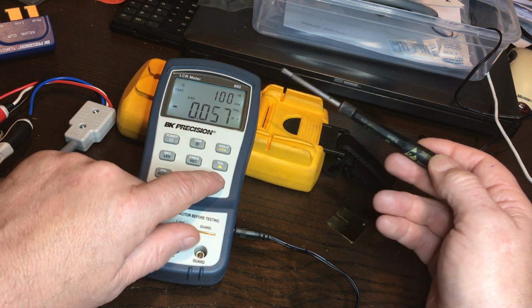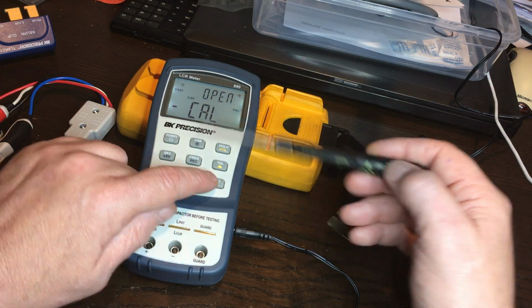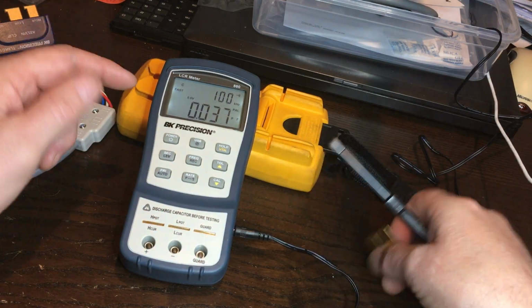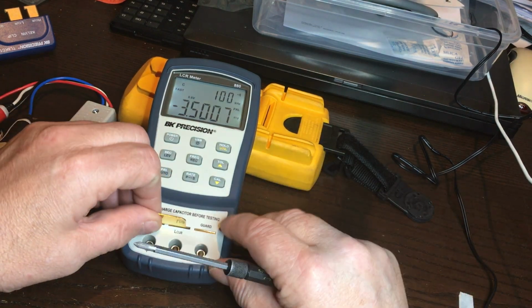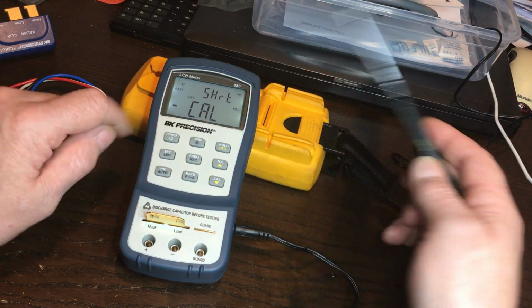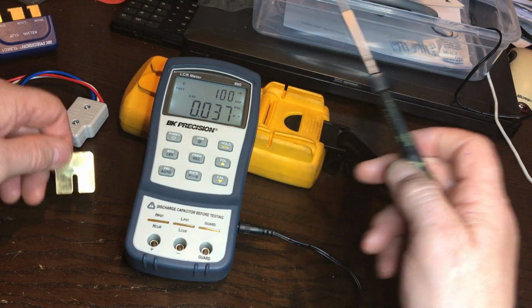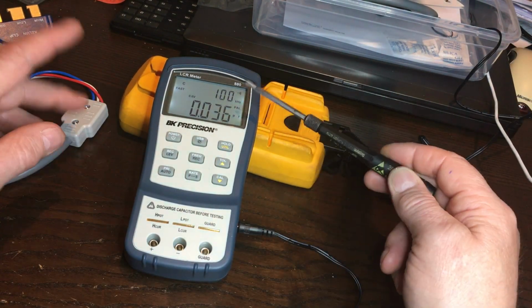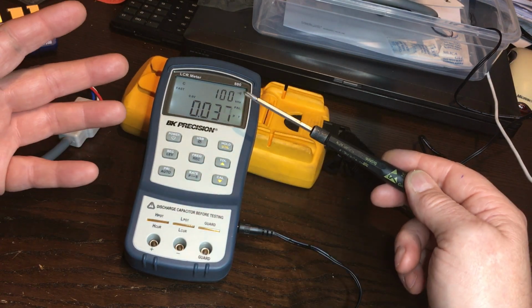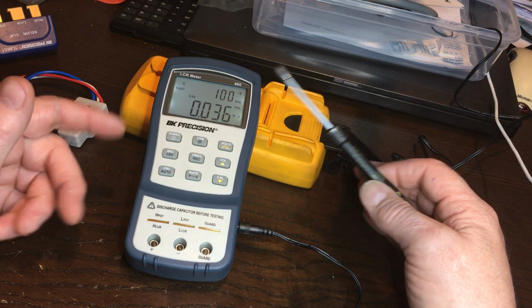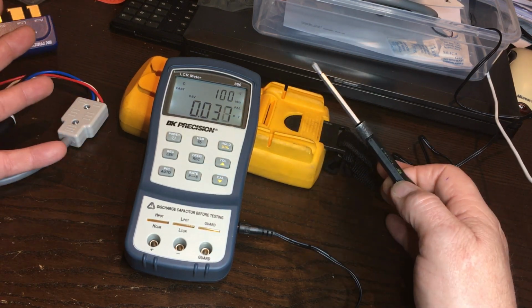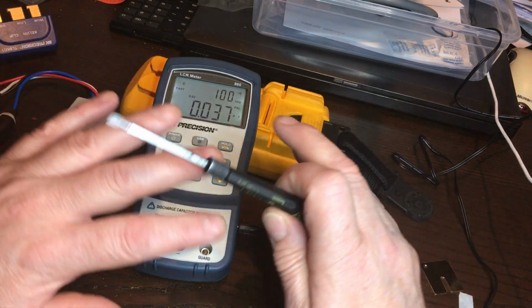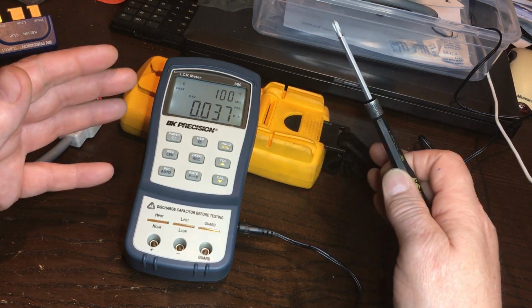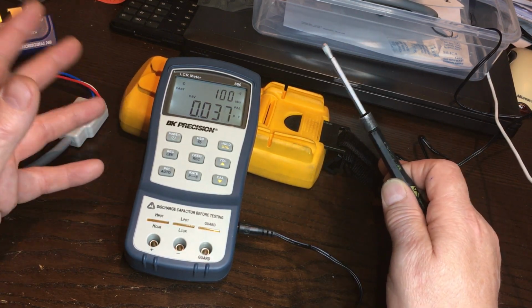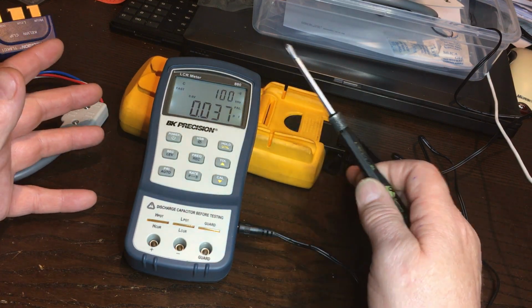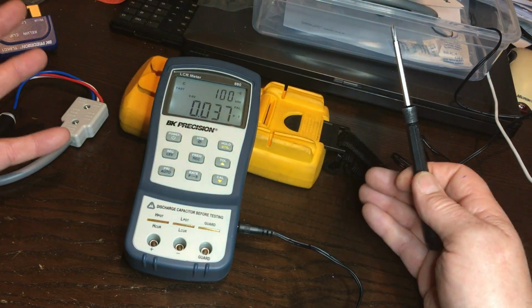It has a calibration. You have to calibrate it for an open position. Now it's open. Press it again. That's the open. If you put in the short plate, it says calibrator short. Press it again, and now it's completely calibrated, but it is calibrated for 100 kilohertz. If you change the frequency, you have to recalibrate if you want the highest accuracy. If you just want to do a normal measurement, you know, the accuracy is not all that important. You can do without the calibration. It is not explicitly necessary every time. Okay? It will still do a measurement, but it will not get the last digits in accuracy.